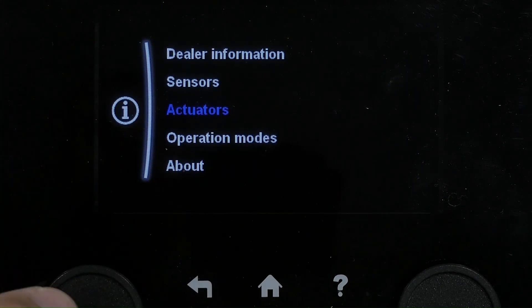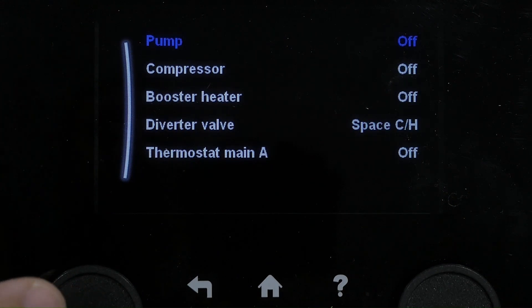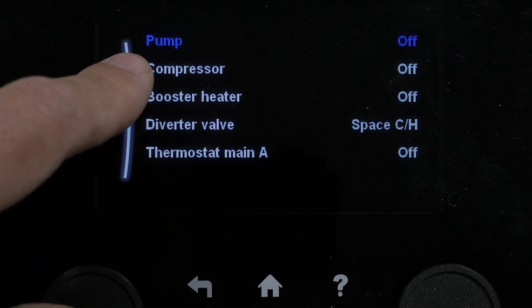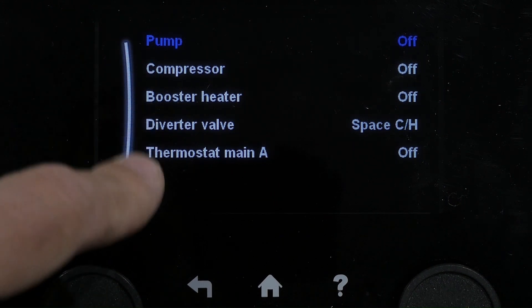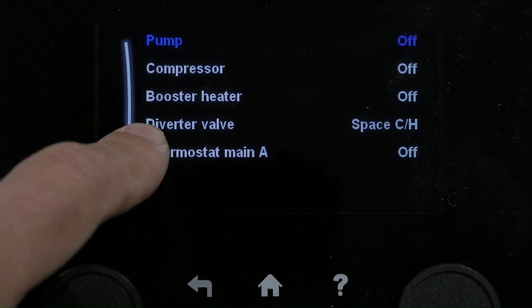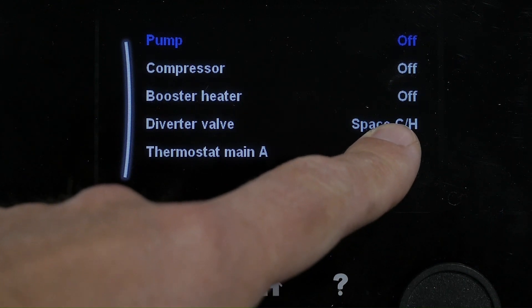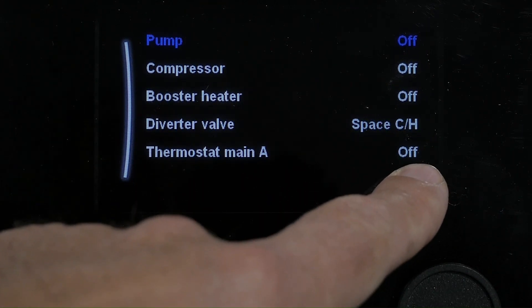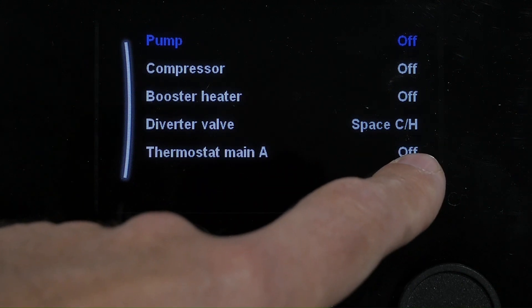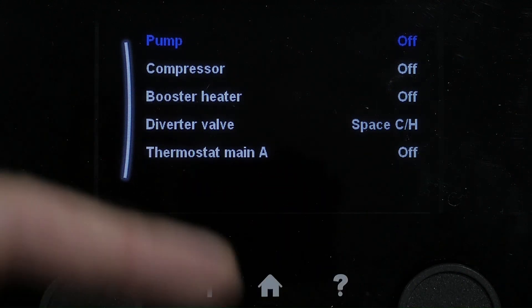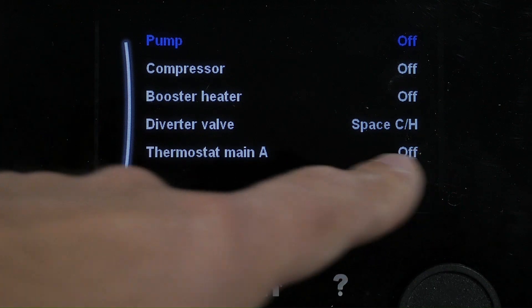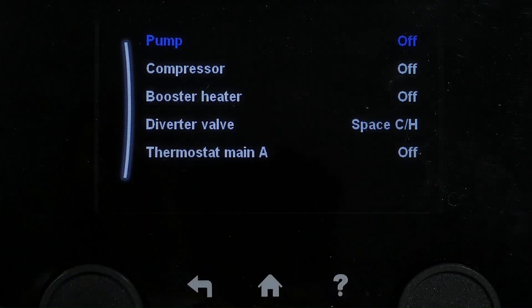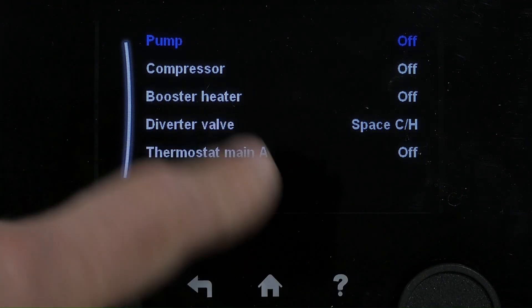Actuators are important as well. If you go into that, you can actually see what is and isn't running. At the moment our pump is off, our compressor is off, our boost heat is off, and our divert valve is actually in space heating mode. Thermostat main A, which is our room thermostats, currently has no demand — they are switched off. So there's a good way of checking that your room stats are signalling correctly to the heat pump: turn those on and off and you should see that turn on and off.